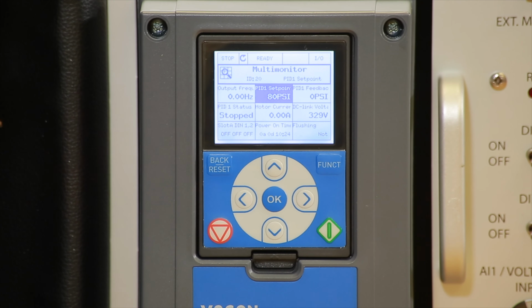The next one is power on time. So this is an elapsed time meter. It'll tell you how long the drive has been running for. It's a fantastic thing. Flushing. We have set up the second digital input if you want to flush the lines at a predetermined frequency. No matter what the drive is running, if you have a selector switch that says flush the lines, we can see how this is going to run shortly. So this is an example here. Let's go ahead and run it and see what happens.